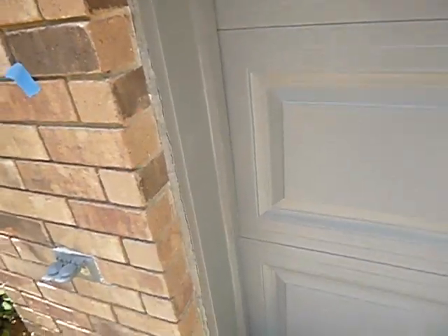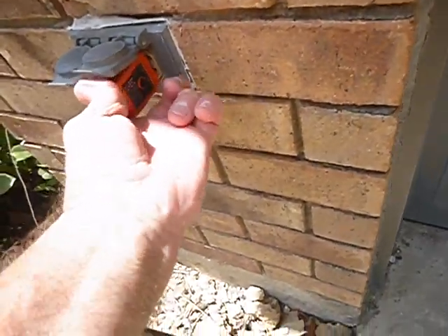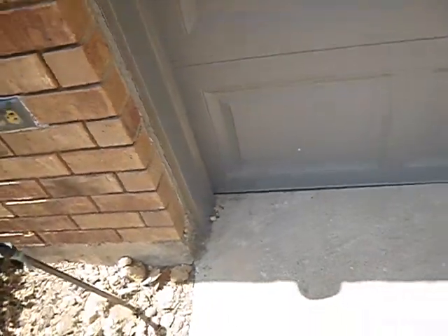The exterior light fixture should be sealed. The receptacle back here did not have the bubble cover, and there's no power now because I already tripped the GFCI on the front. We'll come back and check it.